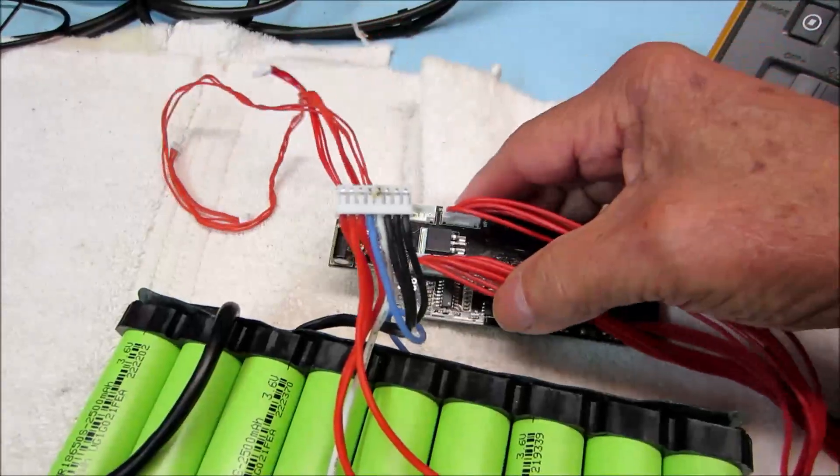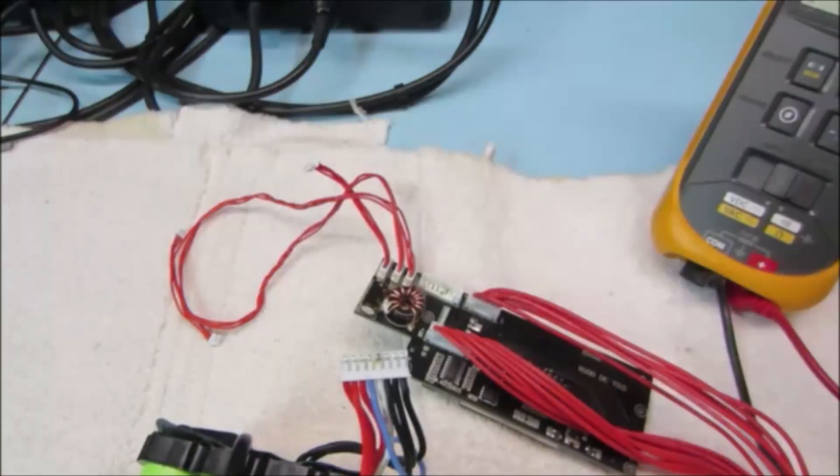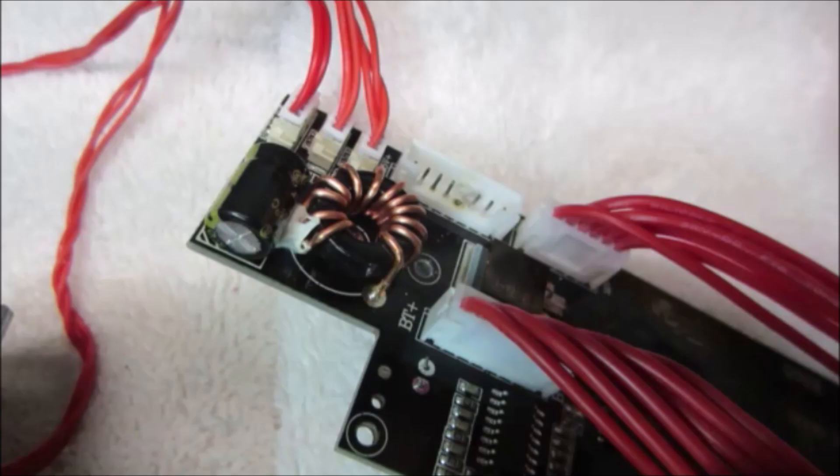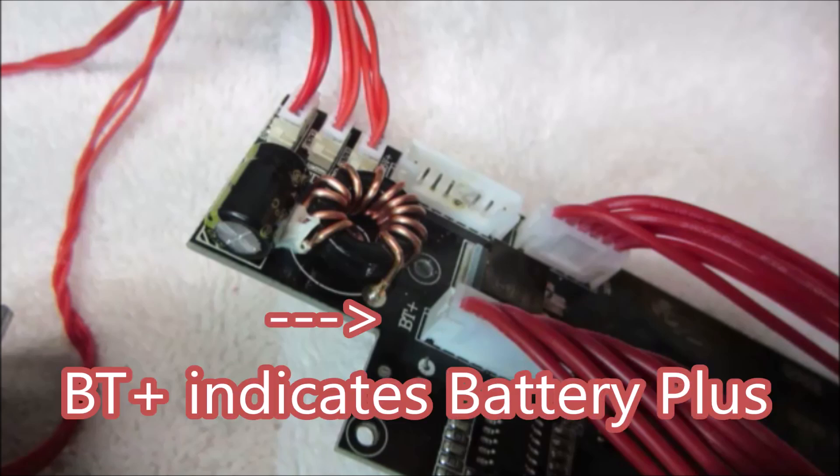So why did this happen? Is this the result of component failure, or are we looking at human error? There are two sockets here, the same size, the same color. Would be very easy to mix up where the plugs go.